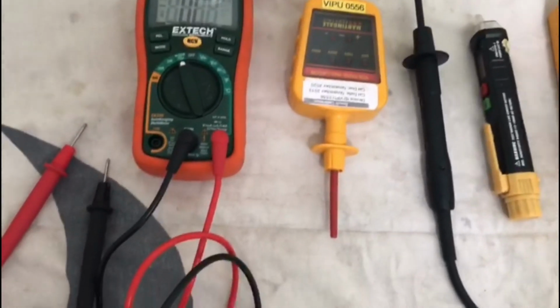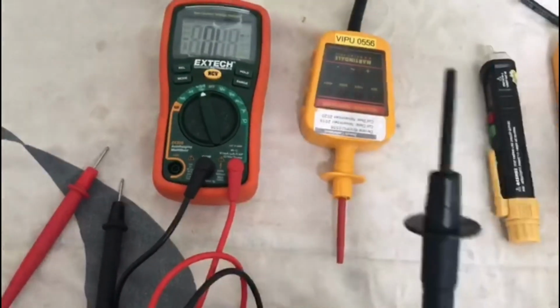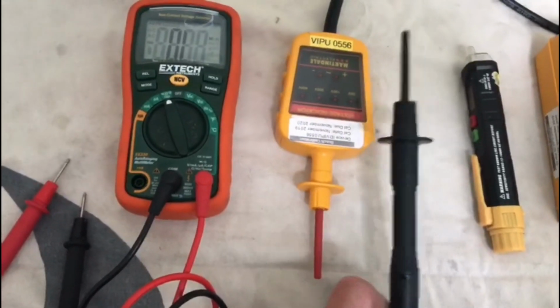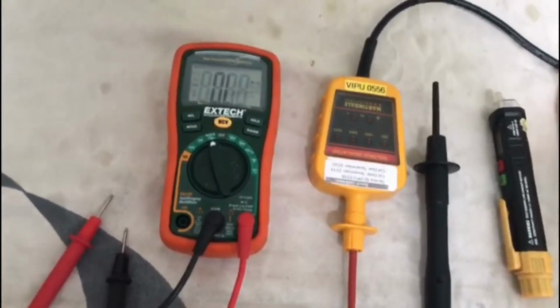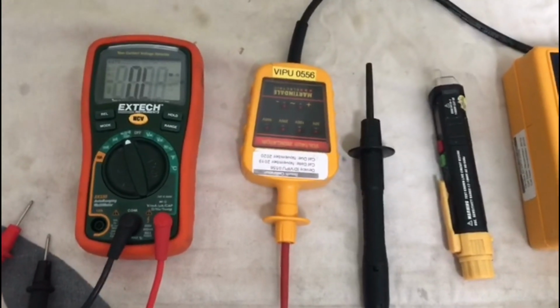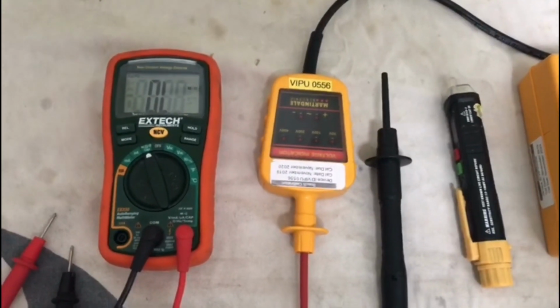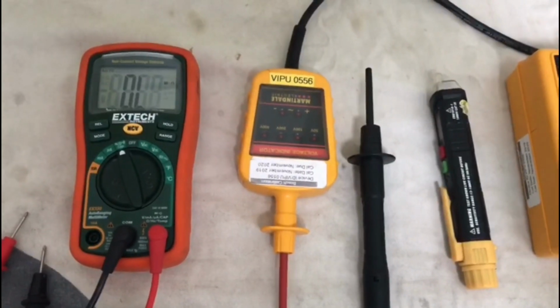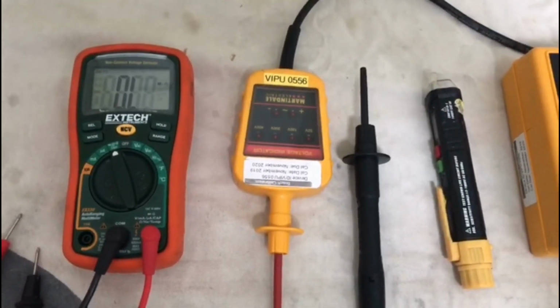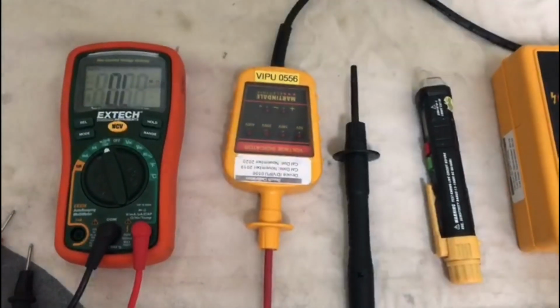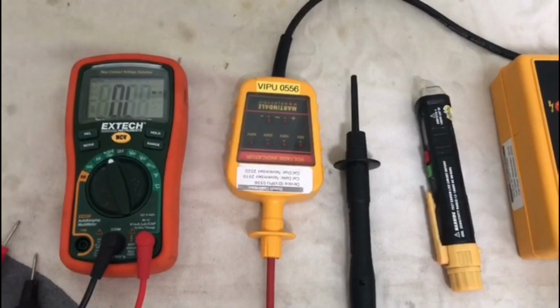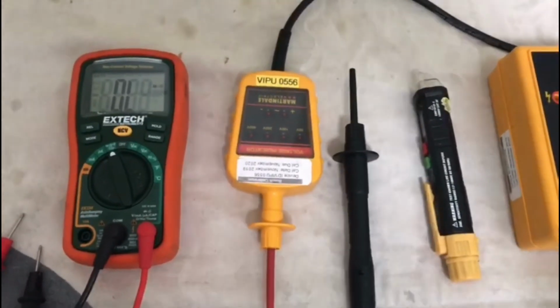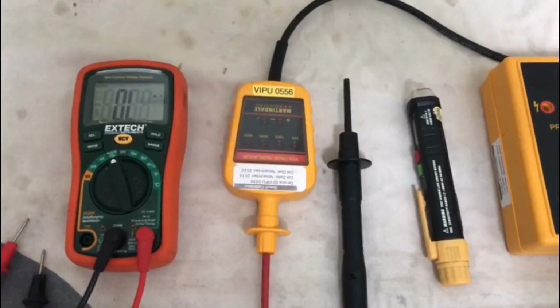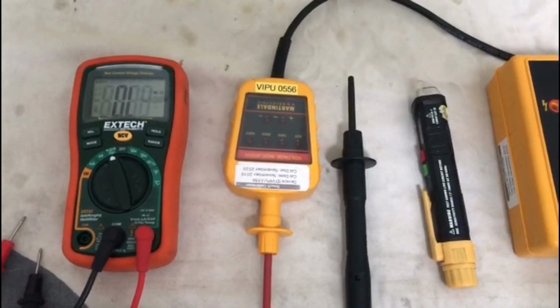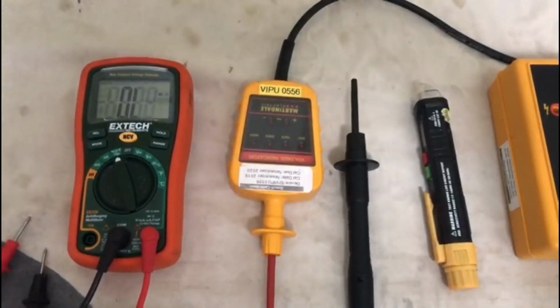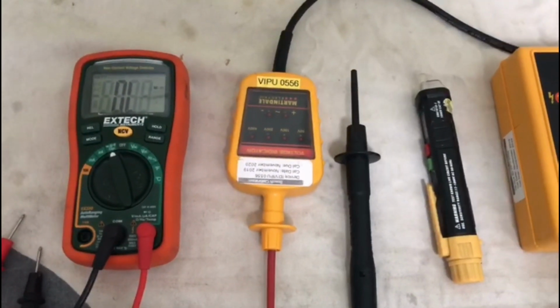The next one you've got is a voltage tester, which will tell you the true voltage of something. It comes with your red probe and an earthing probe, but you always go earth first, then to your live component. Don't do it the opposite way around. You could short things. There's nothing saying that you will, but always go earth first, because that way you're protecting yourself. If you go earth first and you touch a live component and it trips, there'll be no way that you can come into contact with electricity. It's always good practice to test to your earth first.